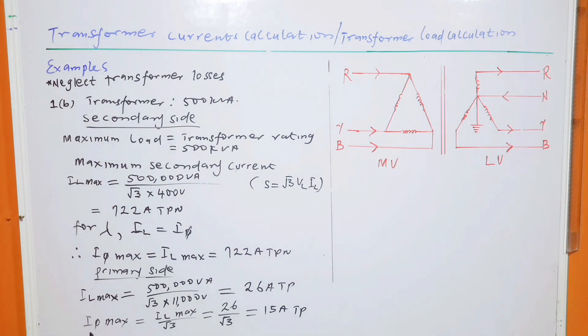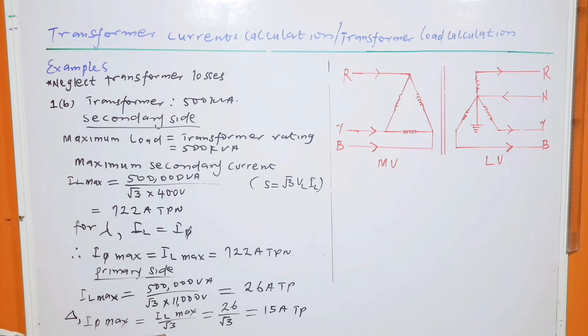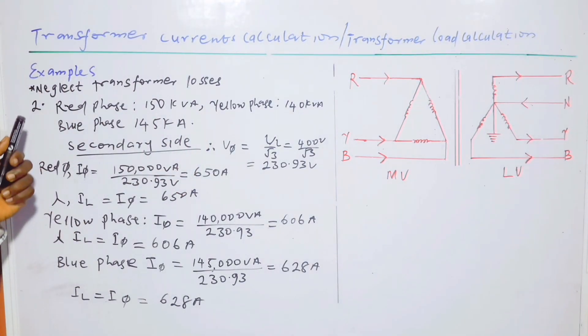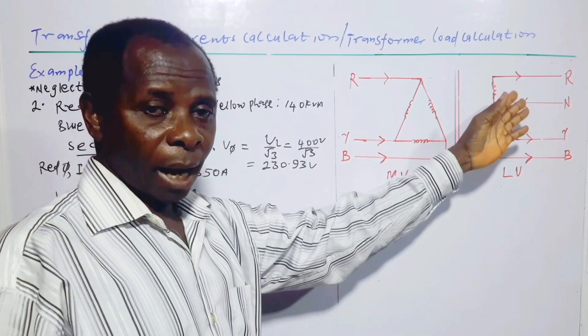For the delta-connected primary, the phase current equals the line current divided by √3. Applying this gives a maximum primary phase current of 15 amperes.